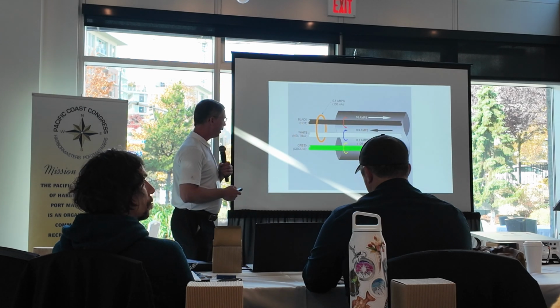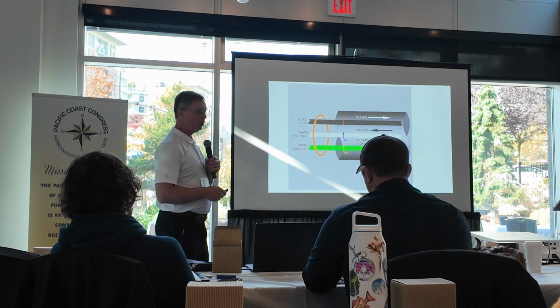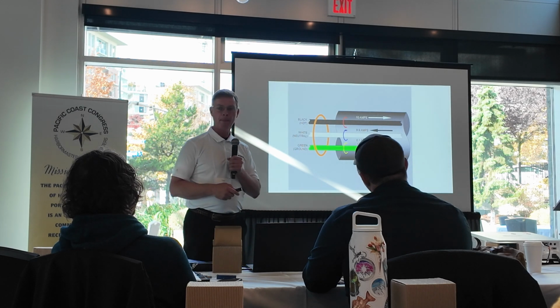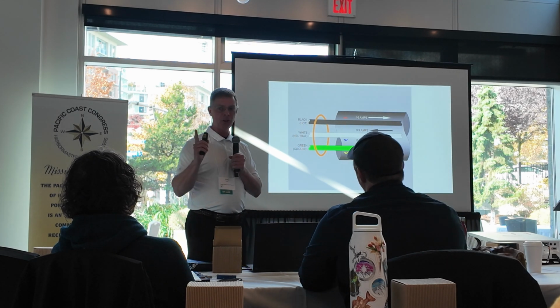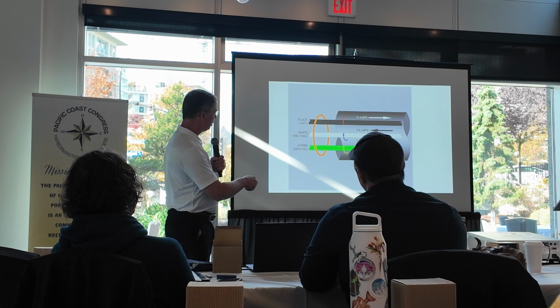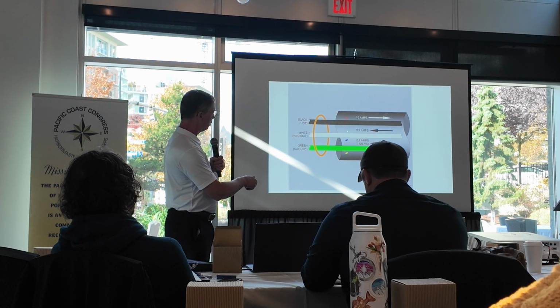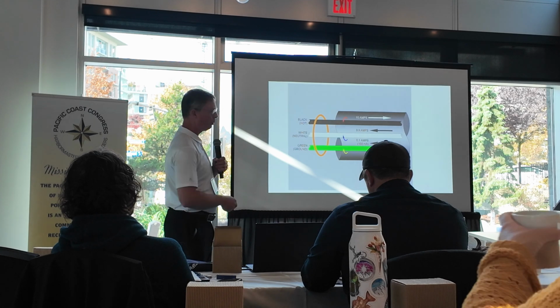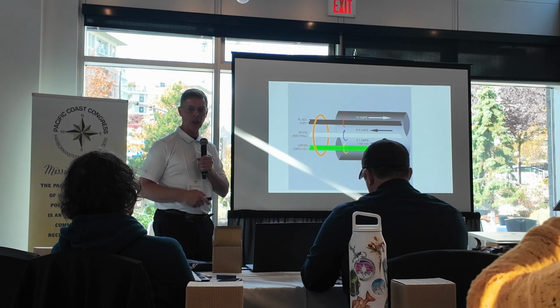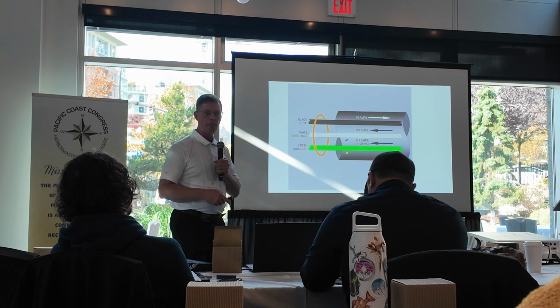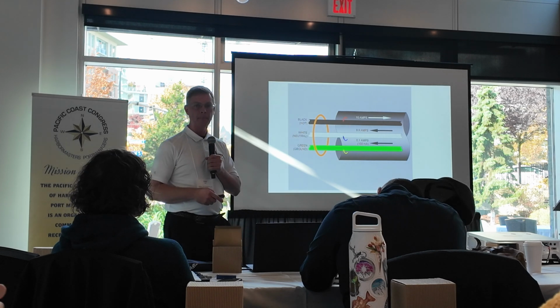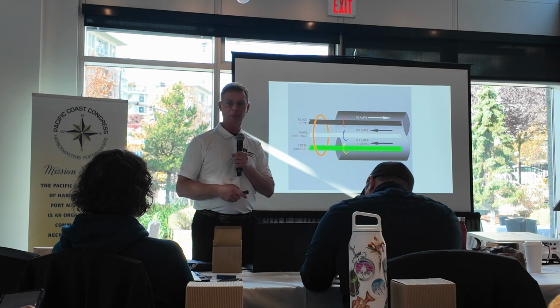Okay? So in this case, if I clamp around all 3, what would I measure? Nope, I read 0. Because if you think about it, I got 10 amps worth of magnetic field there, 9.9 going in that direction, and 0.1 to make up the total of 10 amps going and 10 amps coming. That's that example you showed first with the 3 wires through the CT. That's correct. That's always 0.